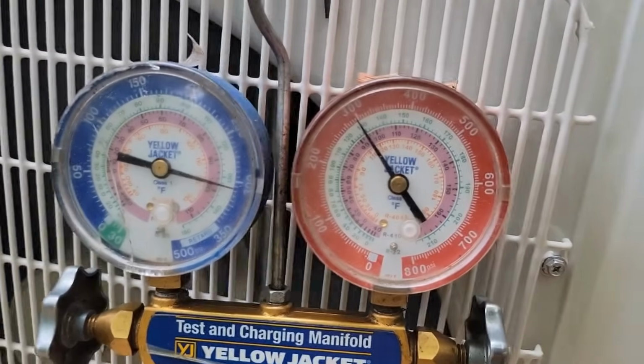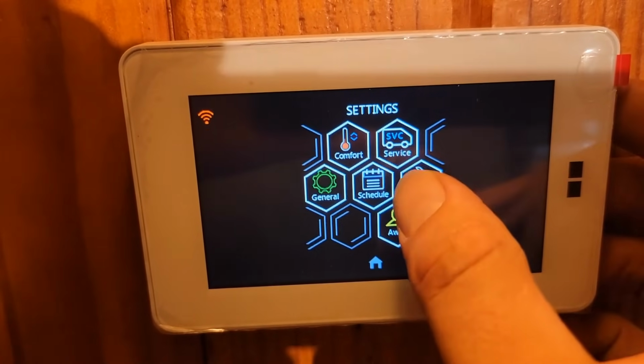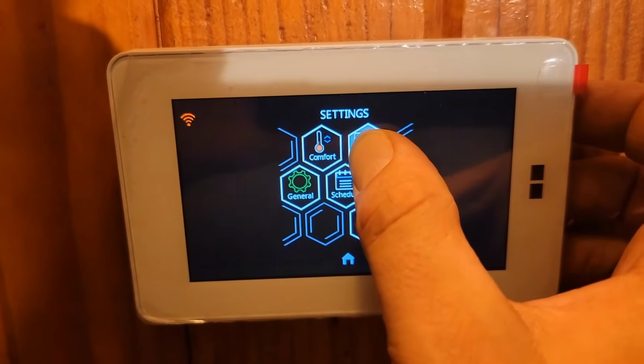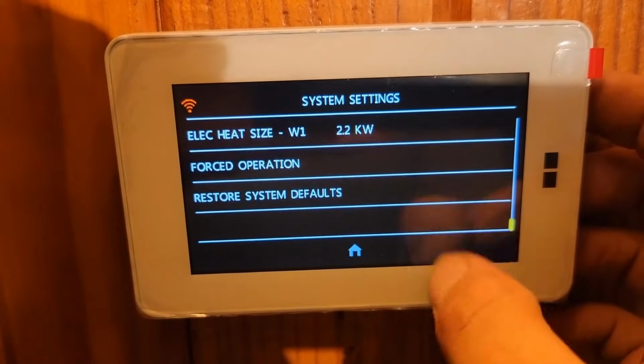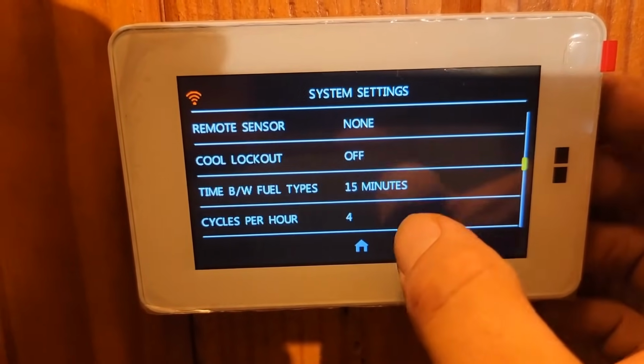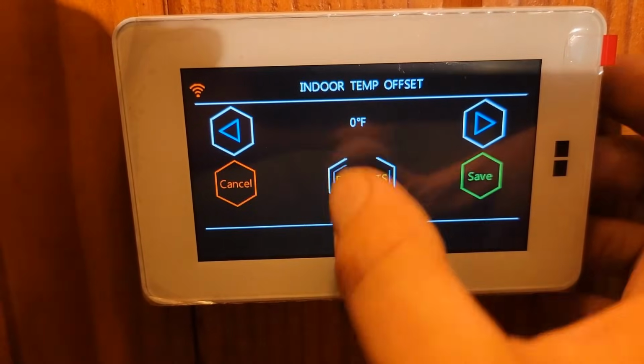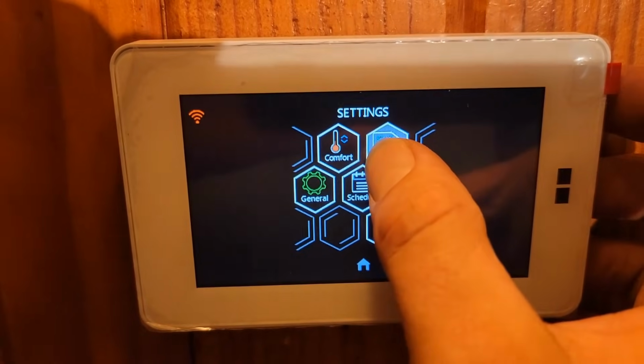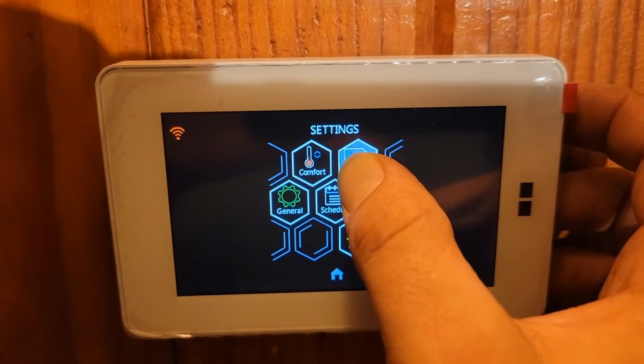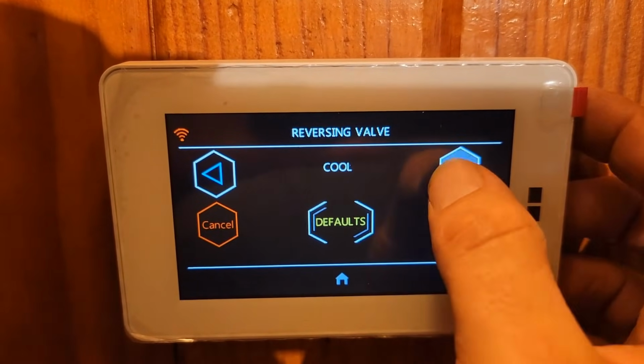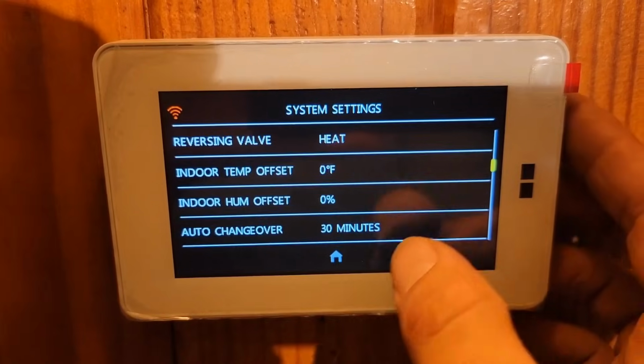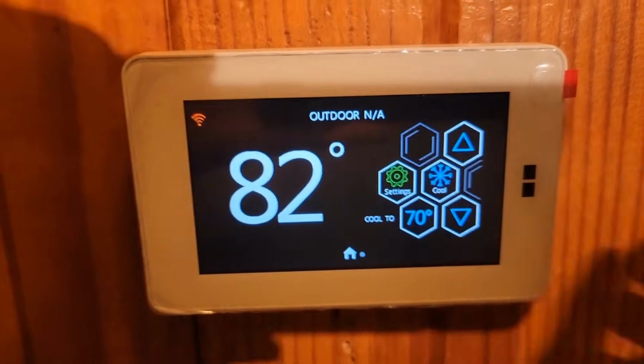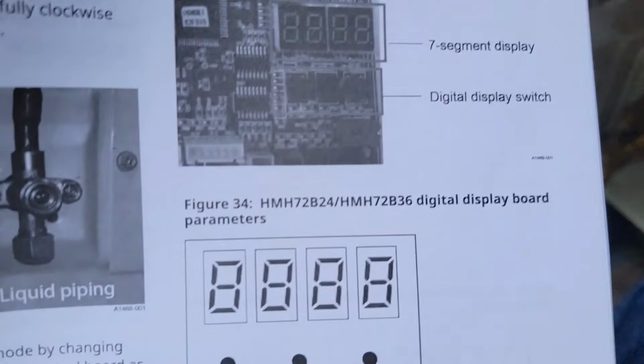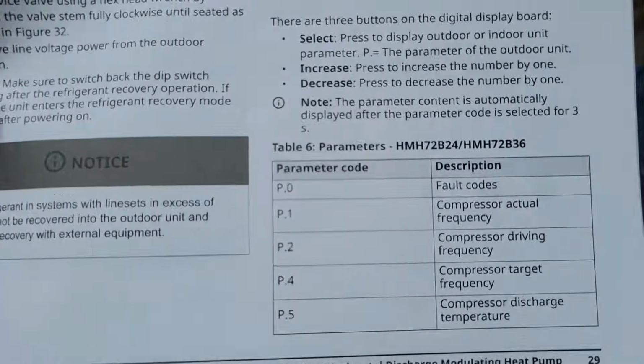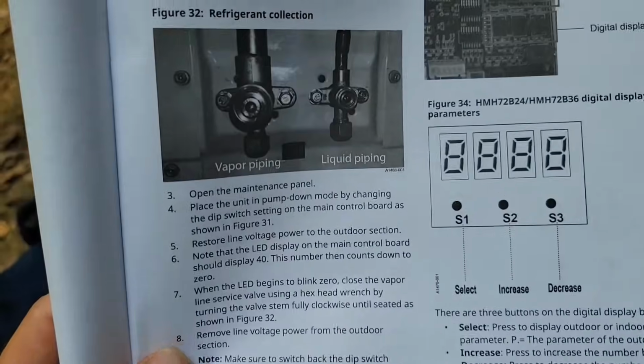And then we should see totally different pressures. All right, here we go. Settings, service, 1, 2, 3, 5. All right, up here. This is where it says reversing valve. Oh, back. Come on. 1, 2, 3, 4, 5. Reverse valve cooling, switch to heating. Save. All right, that should have made the fix there. Got a 0 on the display there. You can see there's some parameter codes. Read your manual, folks. Read your manual.